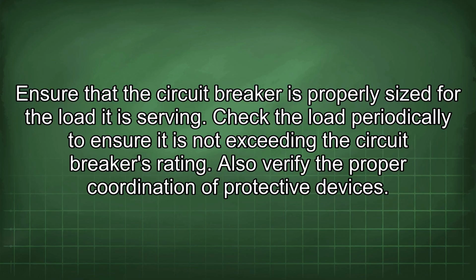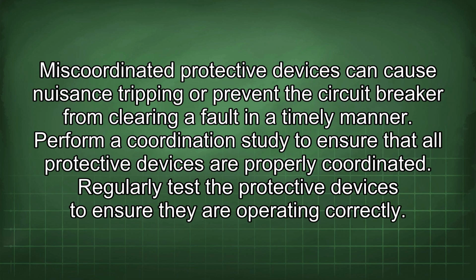Also verify the proper coordination of protective devices. Miscoordinated protective devices can cause nuisance tripping or prevent the circuit breaker from clearing a fault in a timely manner. Perform a coordination study to ensure that all protective devices are properly coordinated. Regularly test the protective devices to ensure they are operating correctly.